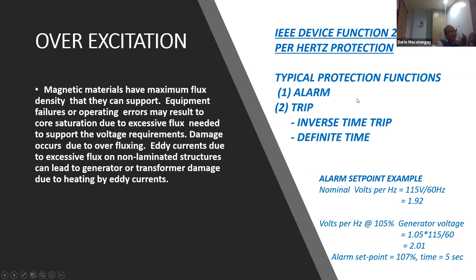So therefore, this is the protection that we need. Typically, it's implemented using an inverse time trip and a definite time trip. When you have an inverse time trip, you have a pickup and a time dial that needs to be set. This is just an example. The nominal setting is the secondary voltage, 115 volts, which correlates to 13,800 volts if the PT ratio is 120, and that's at 60 hertz. So 115 secondary volts divided by 60 is 1.92. If you're operating at 105% voltage, the volts per hertz becomes 2.01.